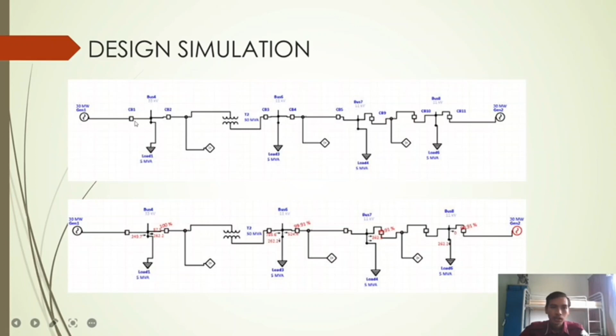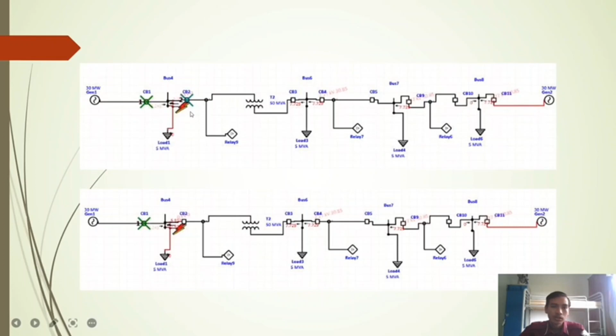So this is the graph of the simulation, and this is the result when the simulation is run. When we put the fault current at bus bar number 1, circuit breaker 1 and circuit breaker 2 will trip because they are the output of relay 9.